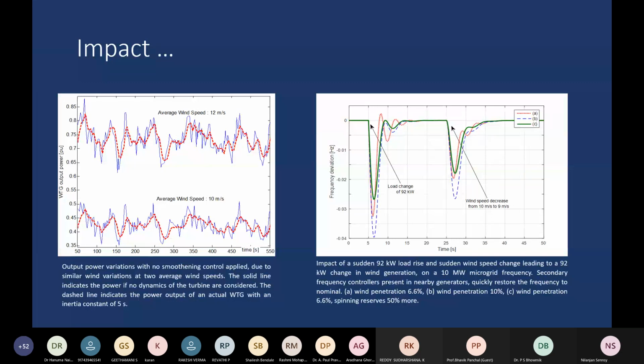The second event is much less severe because the wind inertia, or rather the shaft inertia, is reducing the hammering effect of the event. And the three graphs here, A, B, C, refer to different wind penetrations as well as the availability of spinning reserves. You can see that when the wind penetration is higher, the frequency nadir, which is the lowest point in the frequency because of the event change, is much lower and the frequency change event is more severe.